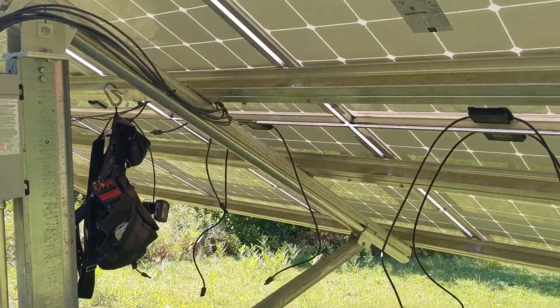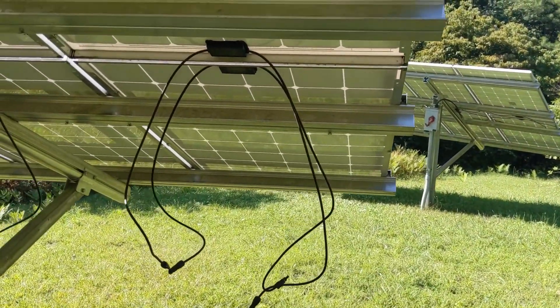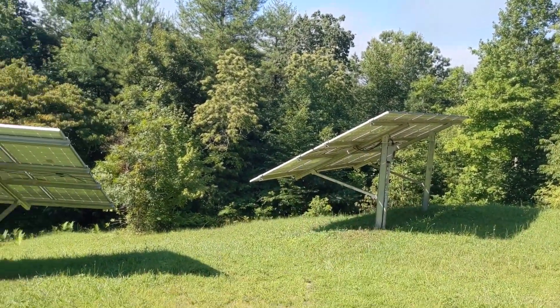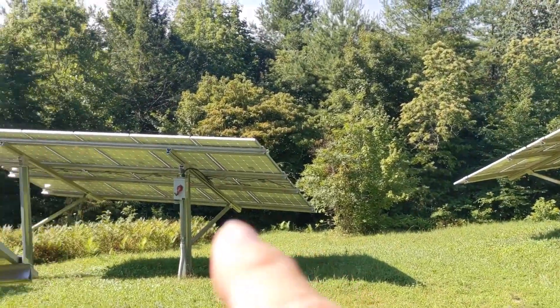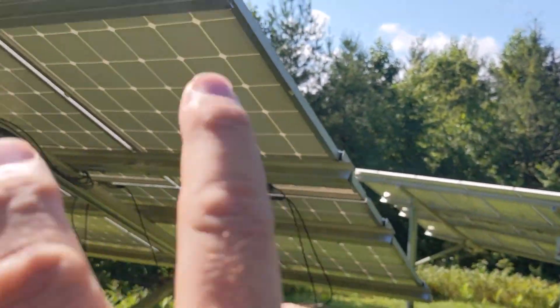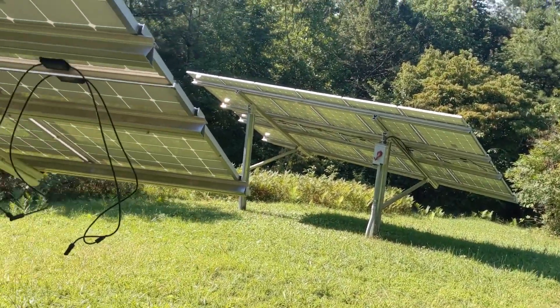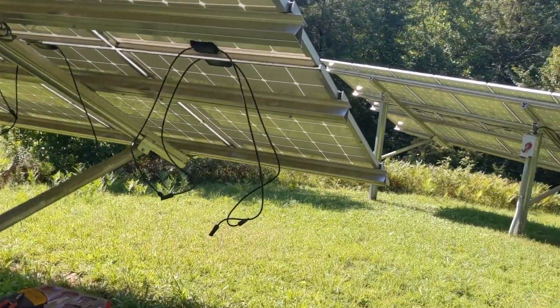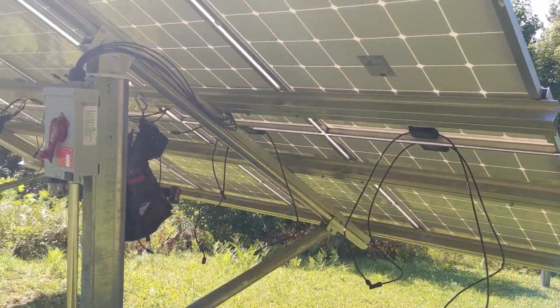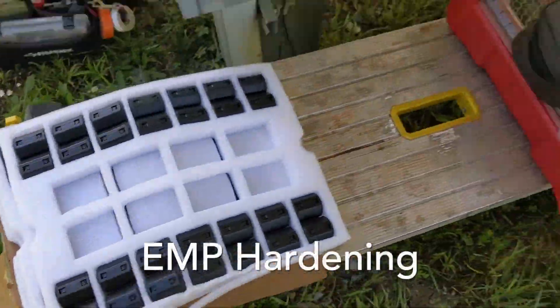For EMP hardening, we're going to put ferrite cores at each junction box on each panel — 36 of those total. We're going to pull from the southwest array and the southeast array — taking six strings from each — combine them, and bring two home runs up to the Sol-Ark. We have some extra wires, which doesn't hurt us at all. Here are the large ferrite cores we put around the CT at each junction box.